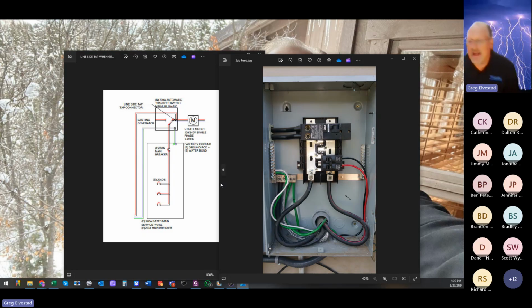But suffice it to say that solar production devices on the market today, most of them require you to be isolated from a standby generator bus. So this transfer switch represents a generator being able to feed the loads, or the utility to be able to feed the loads, and your solar connection comes in here ahead of the switch to keep it isolated from the generator. SolarEdge, for example, says if you do this, you lose the ability to ever replace a service or an inverter that might fail because it was interacting with a generator on the same bus bar. So please be careful of that.